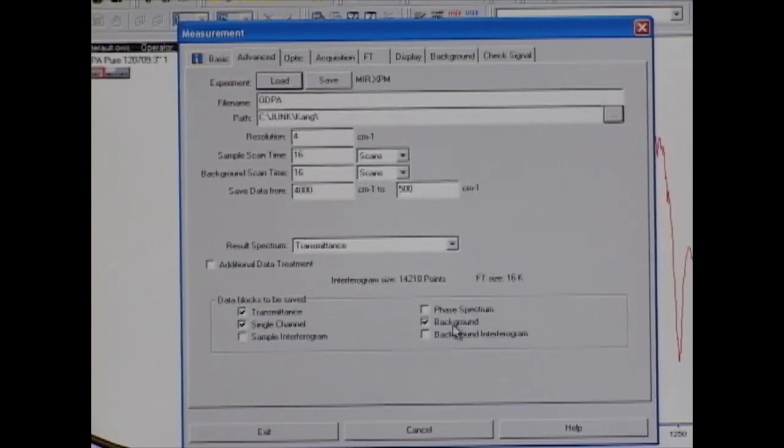Then we go to the Save Data box, which is the range of the spectrum that you want to scan. We want to scan from 4,000 to 500 cm inverse. Then we move on to the Result Spectrum and make sure it is on Transmittance. Then we move on to the Data Blocks to be Saved box, in which we want Transmittance, Single Channel, and Background to be checked.